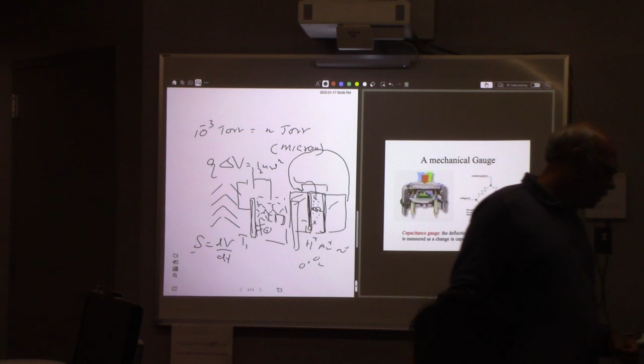The capacitance meter, you've seen this in many systems. It's a very simple thing, it has a diaphragm here with a steady electrode. When you pump the system, this diaphragm will move. Initially at room atmosphere pressure it's like this, and when you pump it curves. When this happens, the capacitance between these two plates becomes different, so they can directly measure the capacitance, which is directly proportional to the pressure. That's how this capacitance gives you the pressure value, very simple.